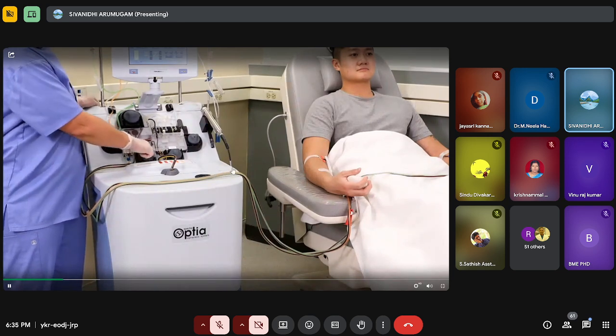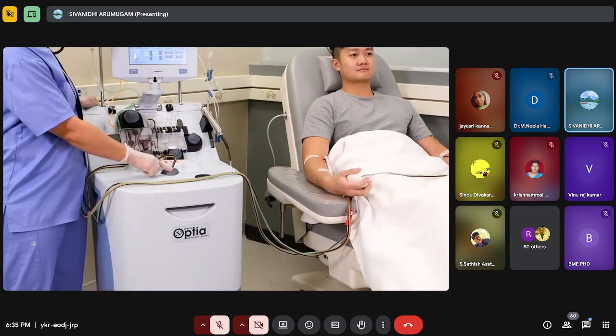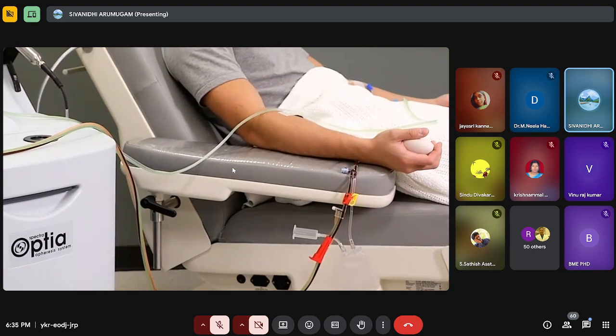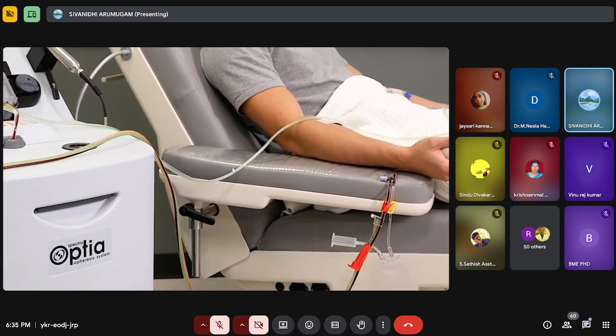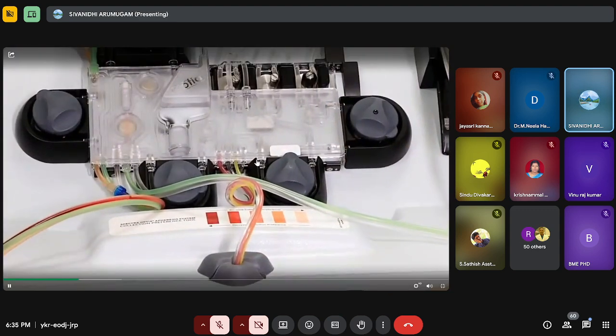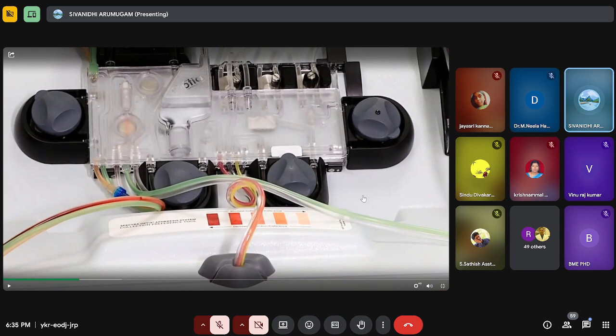The blood is continuously pumped through the tubing set and back to the patient during the procedure. The system cycles through several accumulation and collection phases during the procedure. During each accumulation phase, the chamber fills. I mentioned pumps and valves, right? The main components. We call these the pump rotors. Each pump has its own function.